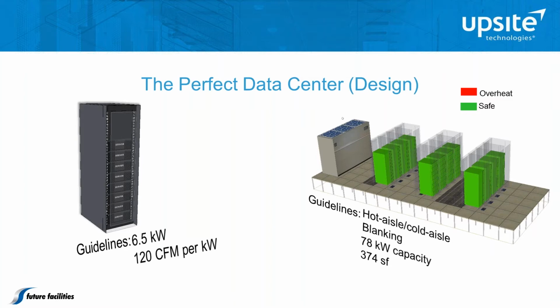Let's look at the design side from a virtual facility point of view. Say an owner-operator wants to design a new small data center, around 80 kilowatts—we've deliberately exaggerated by making it very small. It's a pressurized floor void system, and the engineering company has come up with the standard hot aisle, cold aisle scenario: a single air handler pressurizing the floor void with tiles, guidelines calling for 6.5 kilowatts per cabinet, assuming 120 CFM of cooling per kilowatt.